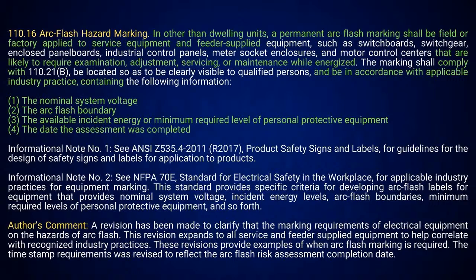Over time we added tables. Now you've got in 70E, table 130.7(C)(15)(a), (b), and (c). I was actually on the task group to help develop those tables, mainly developed for contractors. The reason we did that is because when a contractor goes out on the job, they need to know, and it doesn't matter if you're doing a calculation or using the table, there's 3 pieces of information you have to have. You've got to know the available fault current, short circuit current, whatever you want to call it.